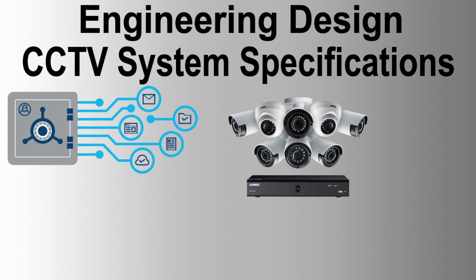CCTV cameras and system design. CCTV system design requirement. General functionality and system architecture. The CCTV monitoring system shall produce full-motion video images, at least 25 frames per second. It shall be an IP-based 100 Mbps Ethernet network platform with control and monitoring, including sequential switchers located in control rooms for all cameras. The architecture of the CCTV monitoring system shall comprise CCTV cameras at main and intermediate pumping stations, main terminals, block valve stations, tie-in stations, and SPM stations.